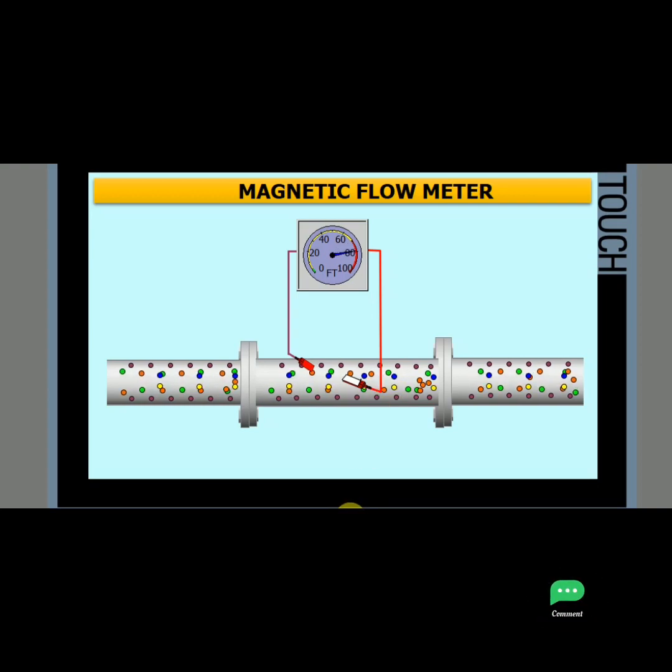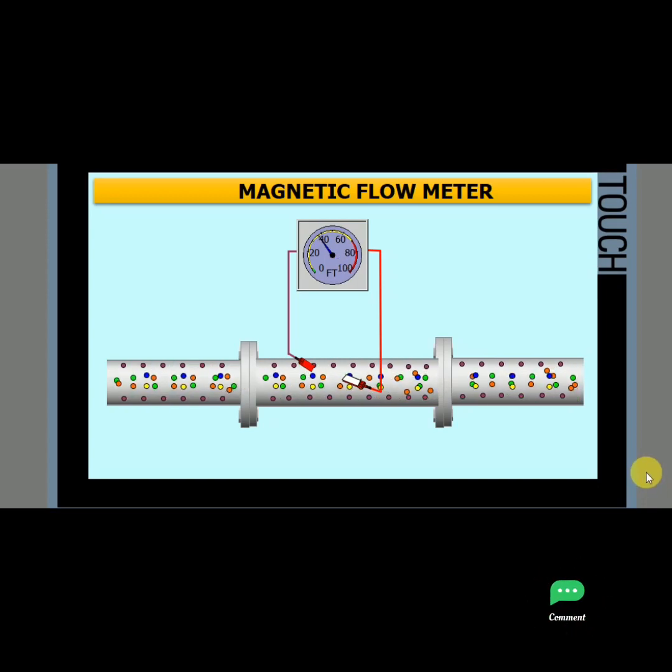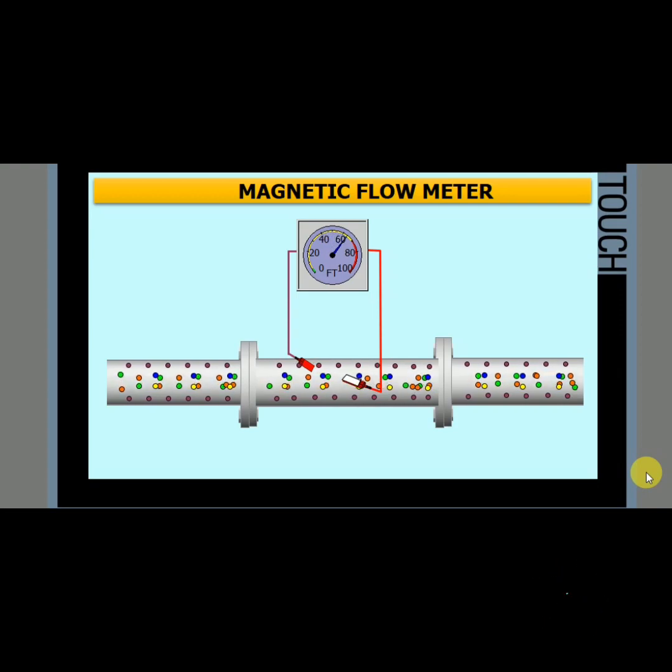Mag meters are typically full bore sensors, meaning that the internal flow path is of the same diameter as the upstream and downstream connections. This construction eliminates any restriction of the fluid which may alter the flow path or create a pressure drop. Fluid passes through the mag meter in a straight line through the bore of the sensor.